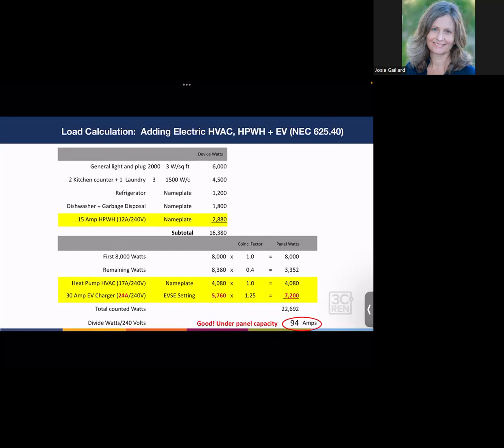That reduces our total device watts to 5,760, times 1.25 gets us to 7,200. Total counted panel watts here are 22,692. Divide again by 240, and hey, look, we're at 94 amps, so we're under 100. So here we have an example where we've electrified the water heater, the heat pump HVAC space heating, and the car charger, and we're under 100 amps.